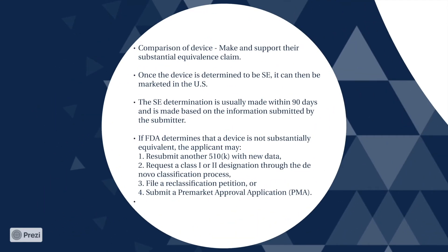What is substantial equivalence? It involves comparing the device to be marketed to a similar or legally marketed device and making a substantial equivalence claim. Once the device is determined to be substantially equivalent, it can be marketed in the US. The substantial equivalence determination is usually made within 90 days, based on the information submitted by the submitter.